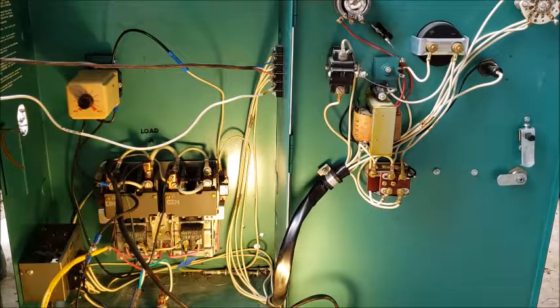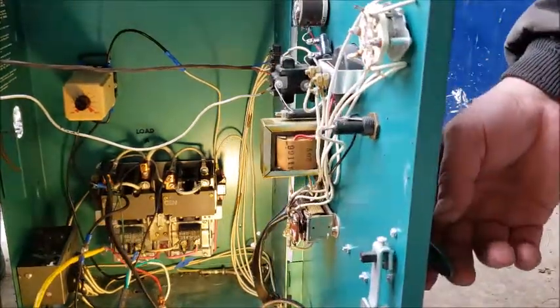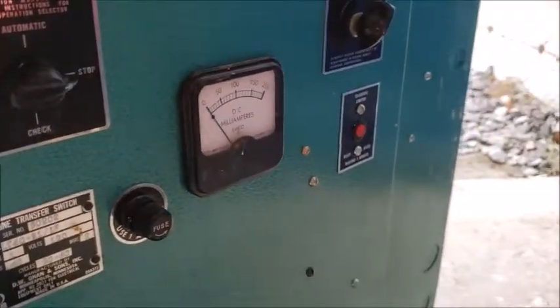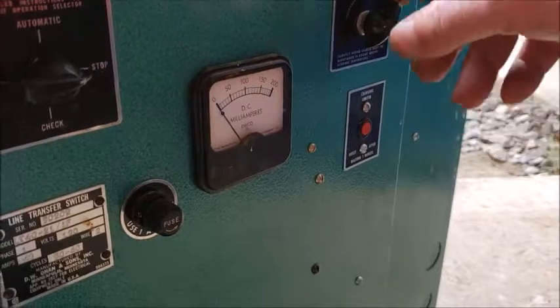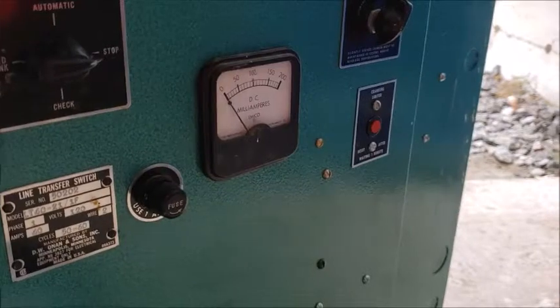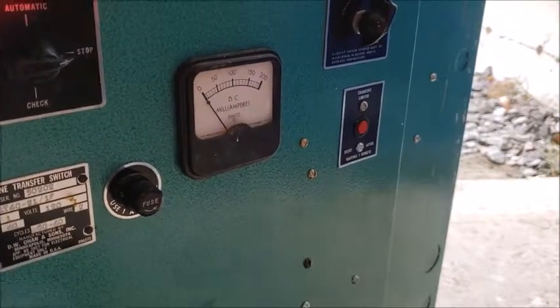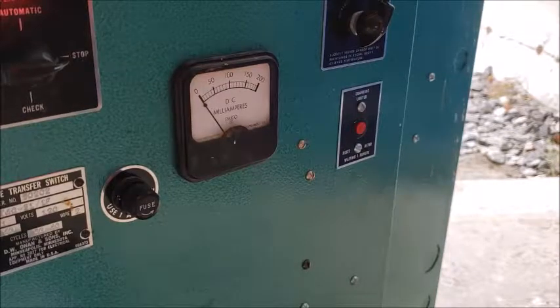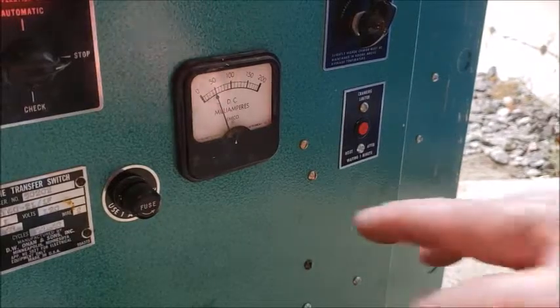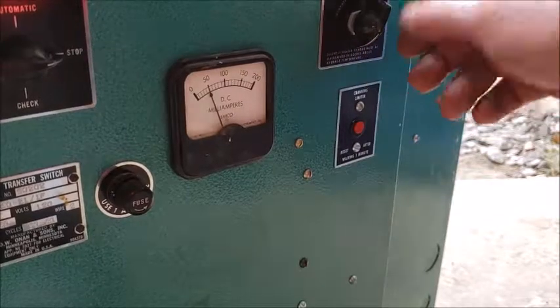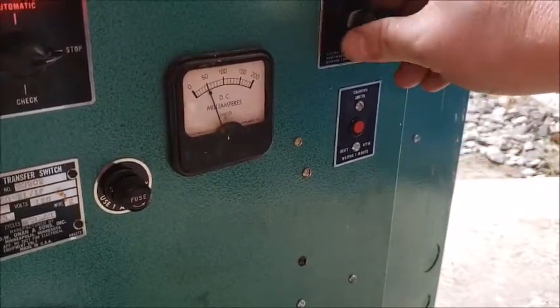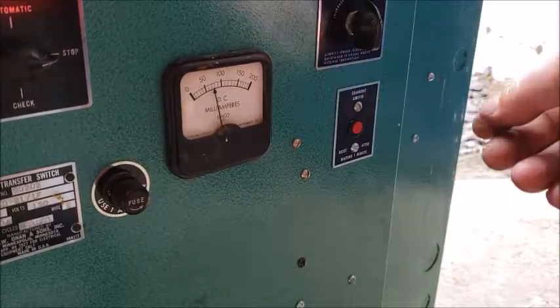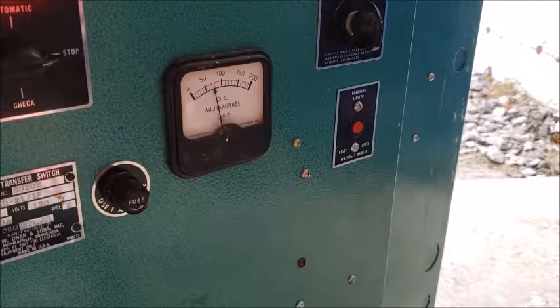Just come around to the front side here a little bit. There's a potentiometer here. Actually let me plug this in so it's actually charging. So it's going to click pretty soon and start charging. Okay, we have 50 milliamps going into the battery. And they say to set this to a place where the battery just stays maintained. So you have to come back periodically and check the battery to make sure it's not overcharging or undercharging. But this adjusts the amount of charge going to the battery.